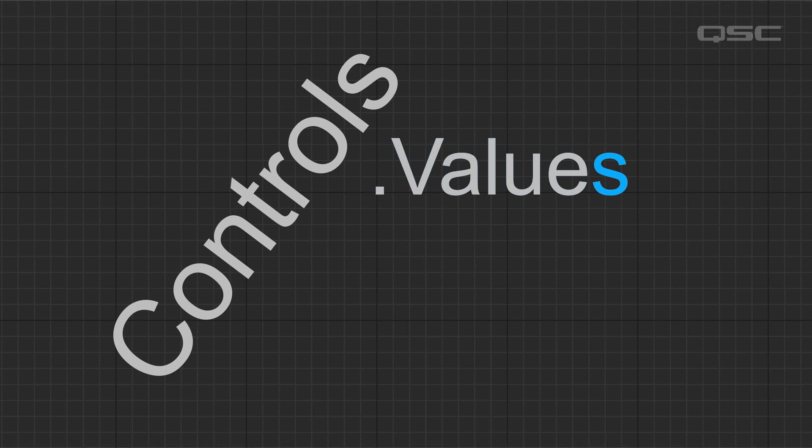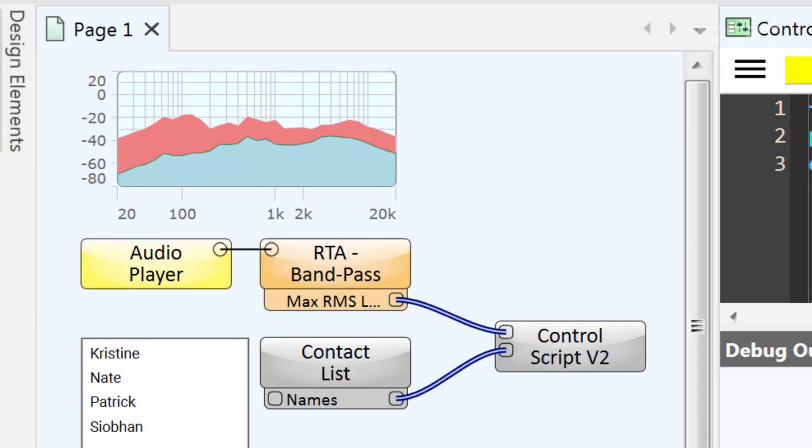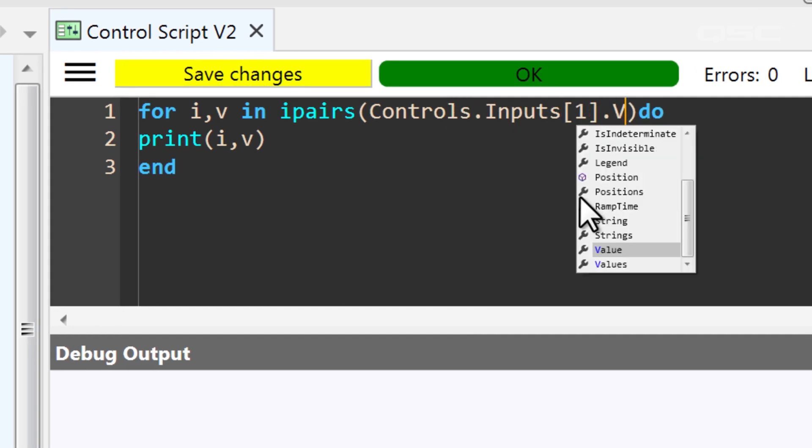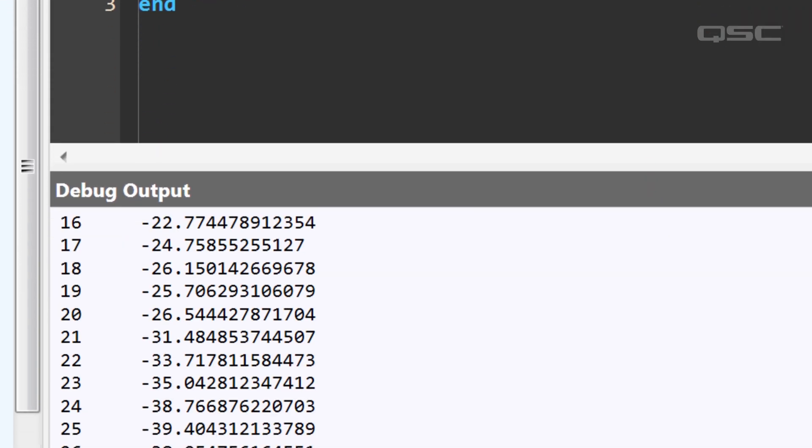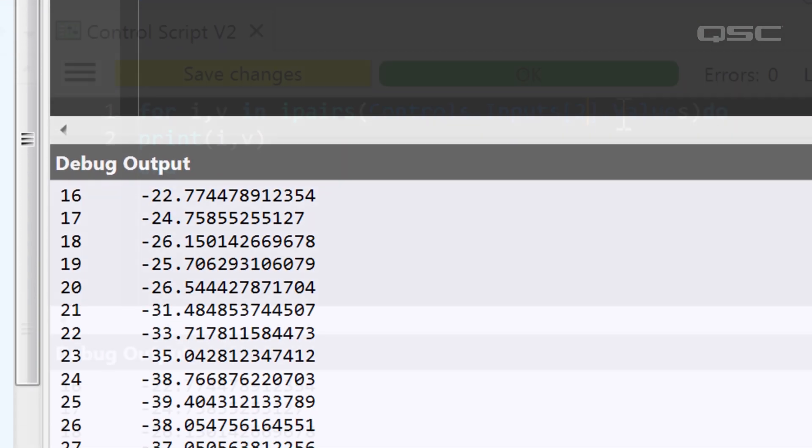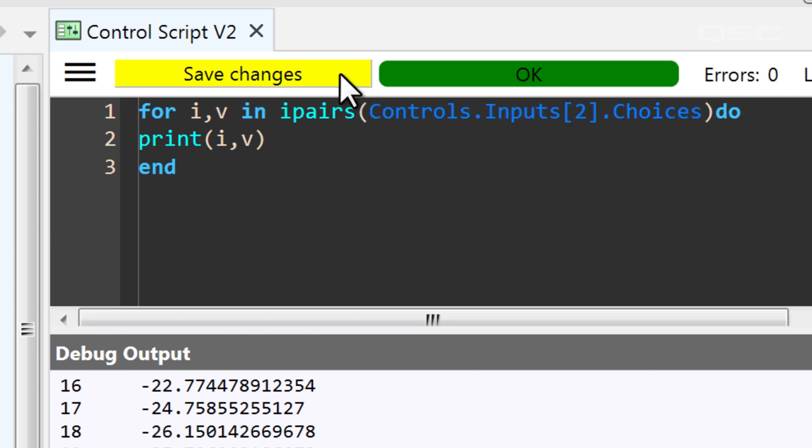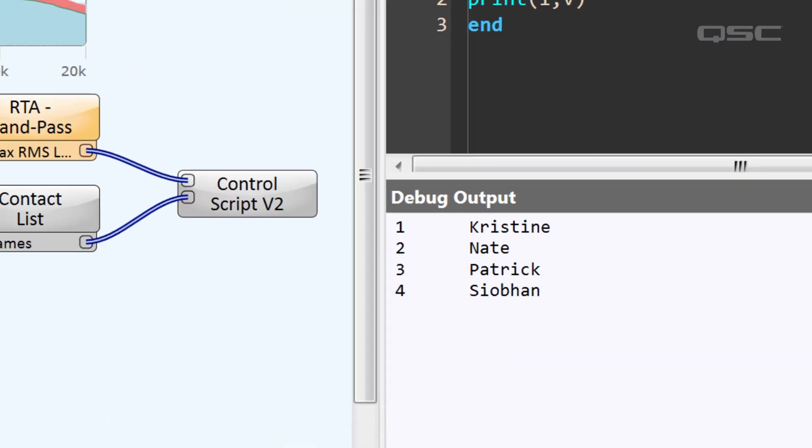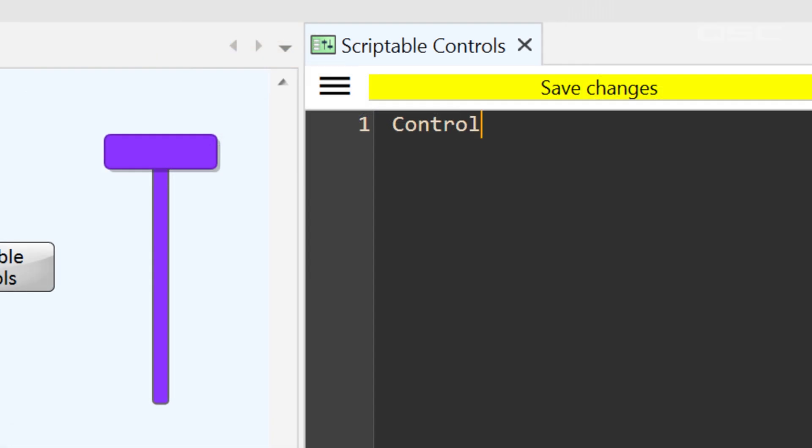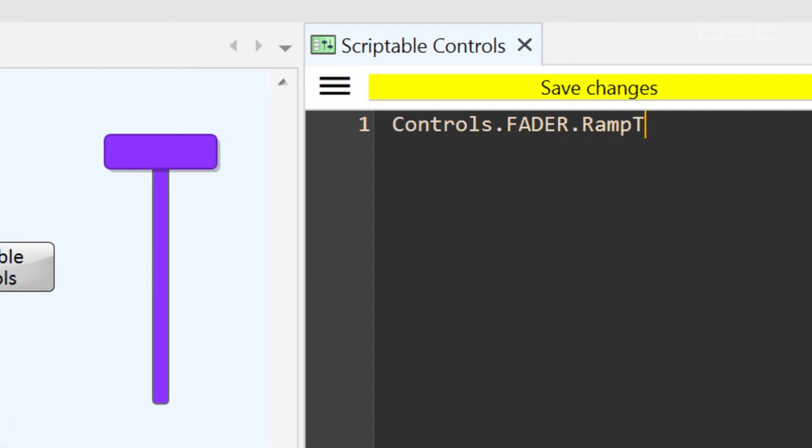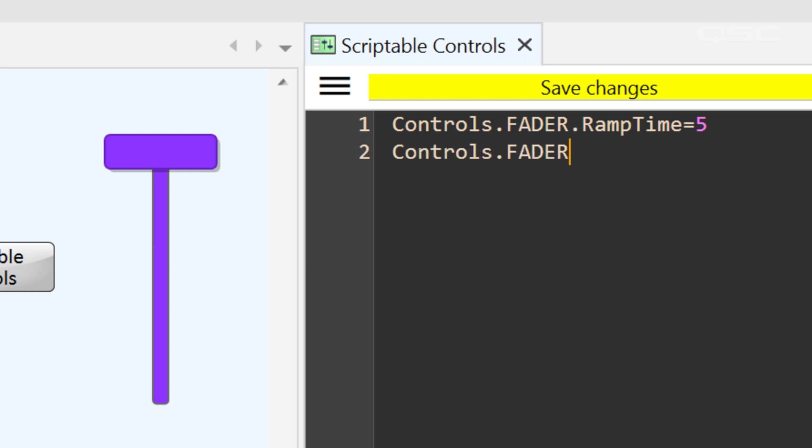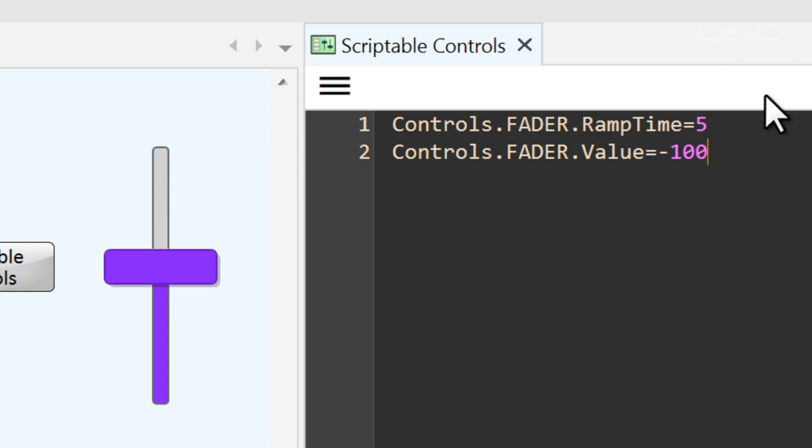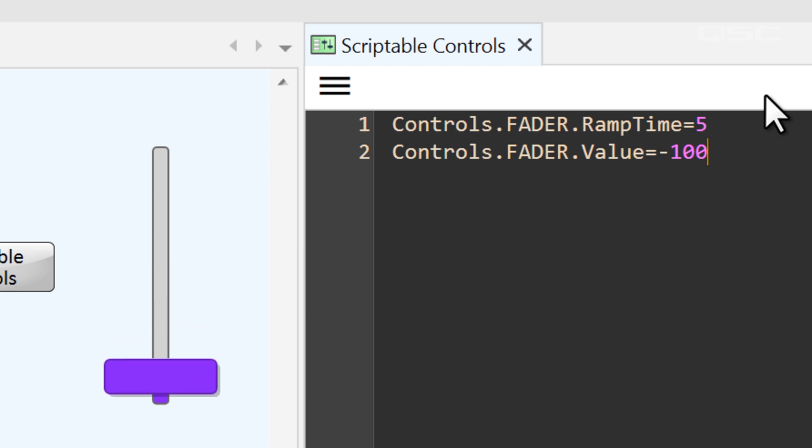Certain types of controls have the .values property. That's plural, values, which is different than .value. For instance, a meter could deliver both a peak and average value as an array using this. There's also a .choices property for controls with drop-down selection menus. For output controls, you might use the .rampTime property to set a length of time for a control to change from one value to another. So, the next time you set that control's .value or .position, it will take this amount of time to arrive there. The .rampTime property is expressed in seconds.